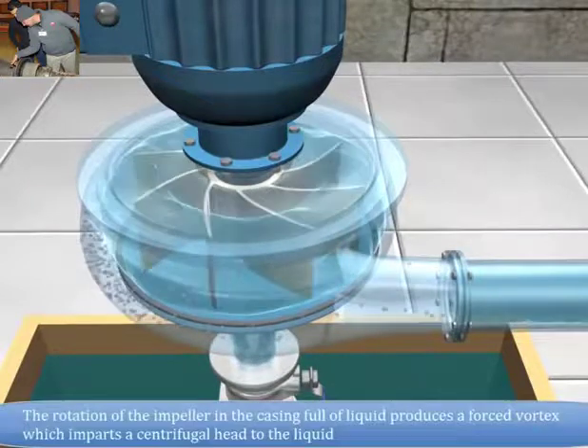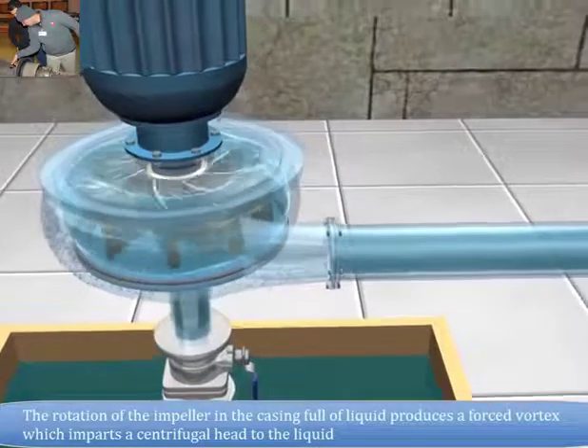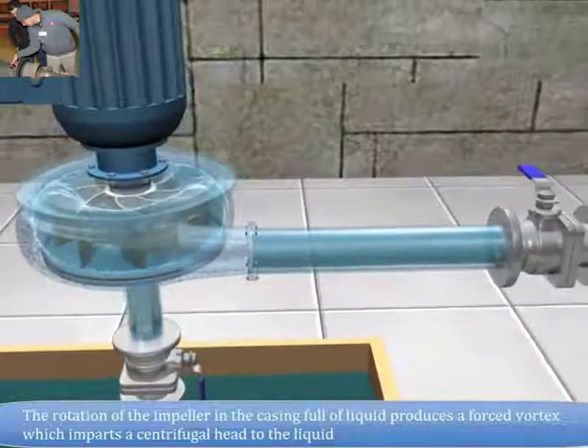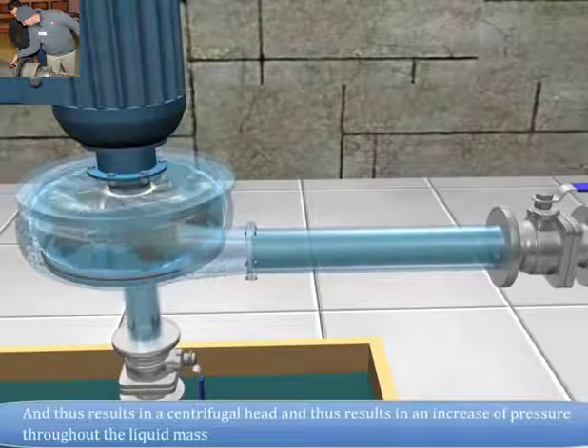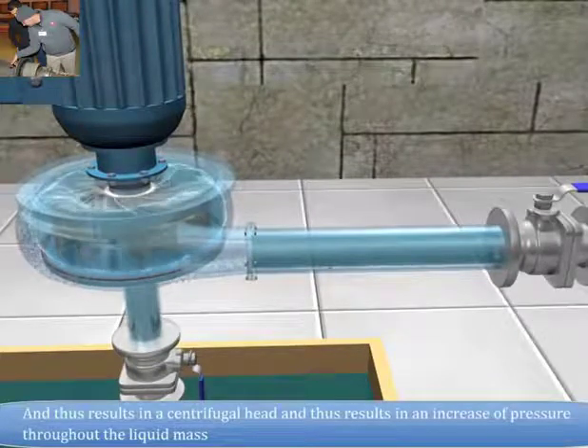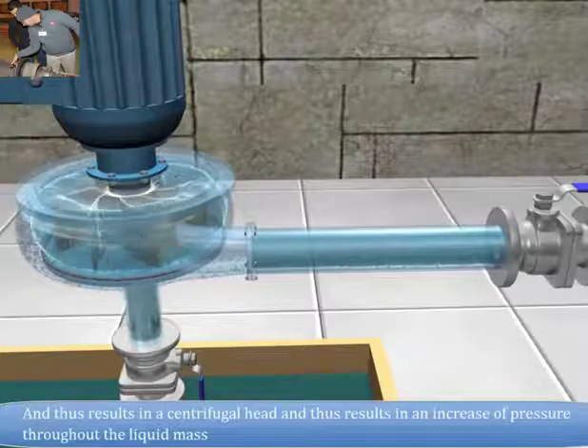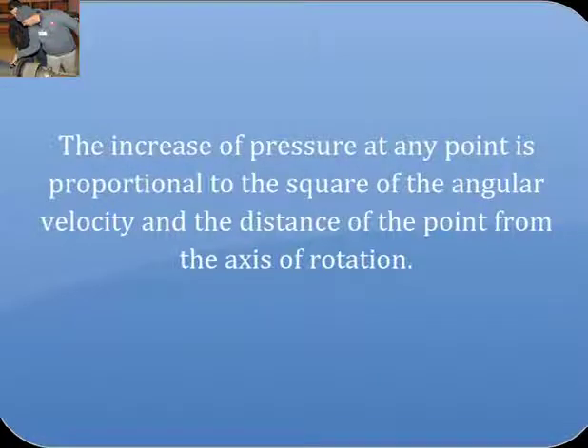The rotation of the impeller in the casing full of liquid produces a forced vortex which imparts a centrifugal head to the liquid and results in an increase of pressure throughout the liquid mass. The increase of pressure at any point is proportional to the square of the angular velocity and the distance of the point from the axis of rotation.